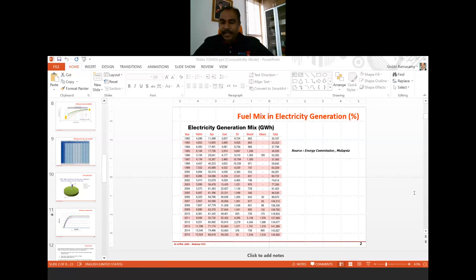Okay. So one thing that you can do for the current system, you say they assume the design stage consultant over-designed. You can check whether it is actually oversized or not by measuring the power of the motor, the pump system. So what is the power value? Based on the power and looking at the nameplate of the pump, you can find out whether the pump is running at light load or not. If it is light load, then you know it is oversized. It is running without VSD, fine.